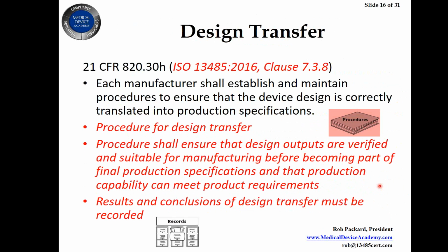Okay, design transfer. So we're rapidly approaching the point where we're going to actually get to the regulation for the design history file. For design transfer, they've added some new language. All the things in red are new. And there's a new requirement for a procedure for design transfer. That wasn't in there before.